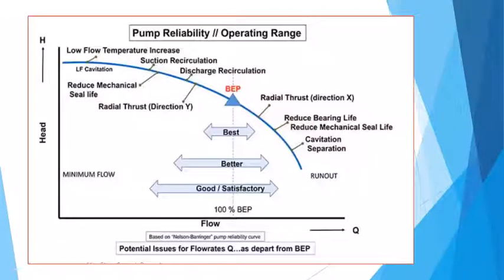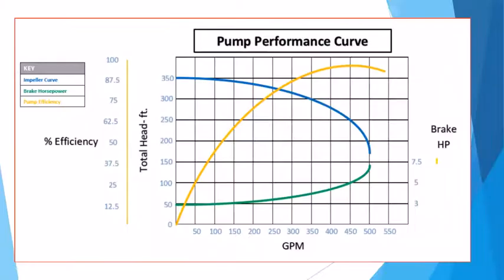So this tool allows you to plug in three different speed ratings where you're going to be running that pump: your lower frequency, your maximum efficiency frequency, and your maximum frequency. Plug that in, and it'll plot where the curves will be, and it'll find out where that best efficiency point is. Very helpful tool. Rob has like 40 years in the pumping industry. Excellent, smart guy. He worked a lot with the large pumping systems, and then went more independent in the industry.